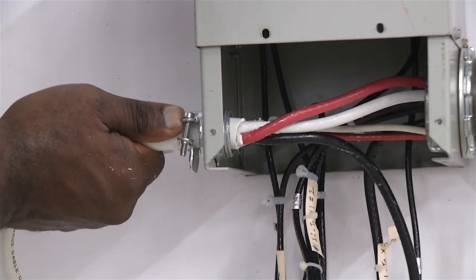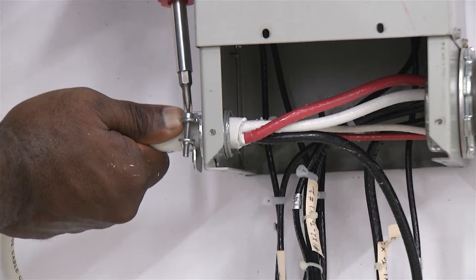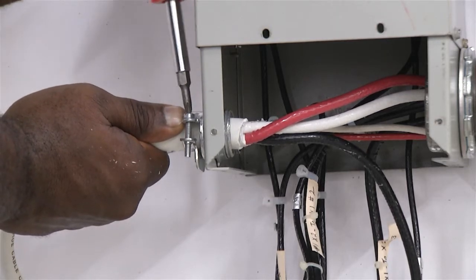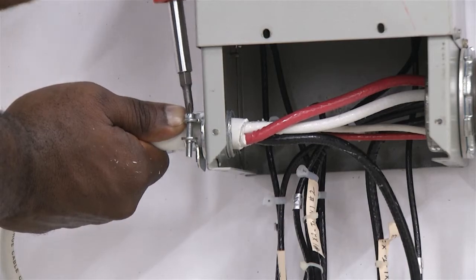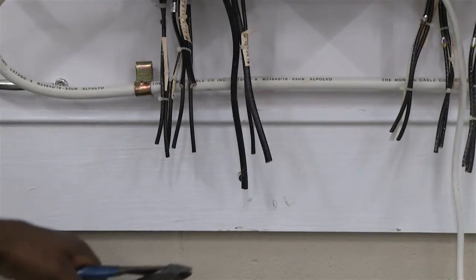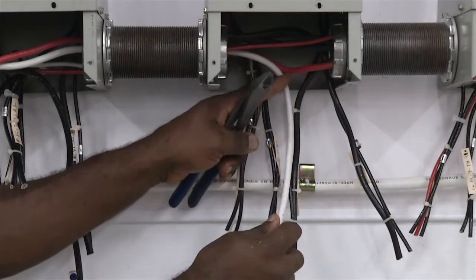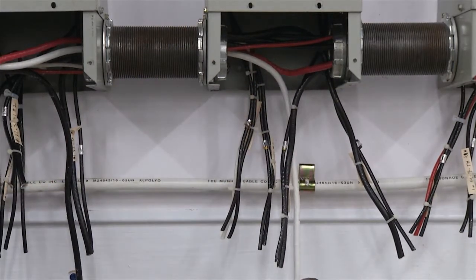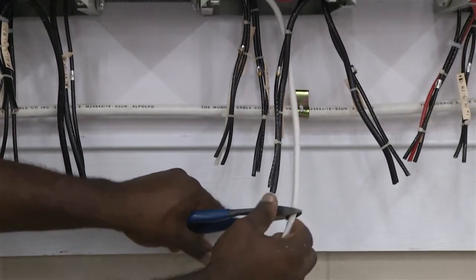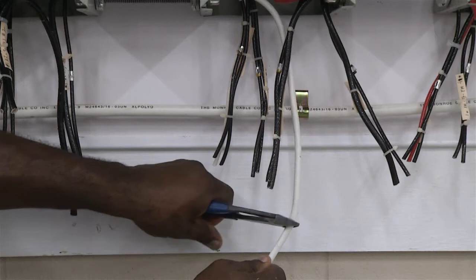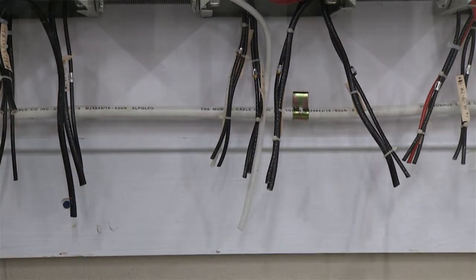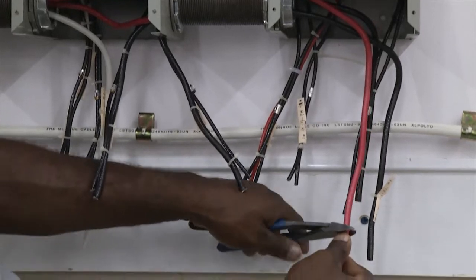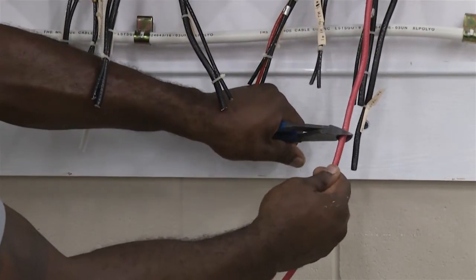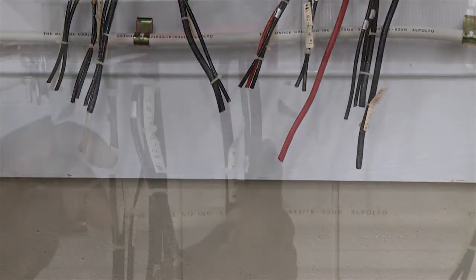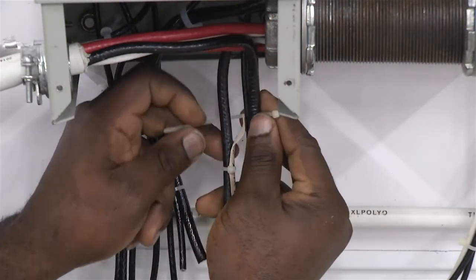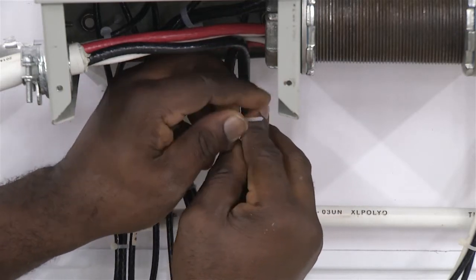Pull the cable back to the 1/8 inch mark that you made earlier and tighten the BX connector to ensure the cable does not slide or move. Cut the leads to a similar length, approximately 8 inches from the bottom of each transformer box. Tie wrap each set of conductors according to the specifications of the wiring diagram.